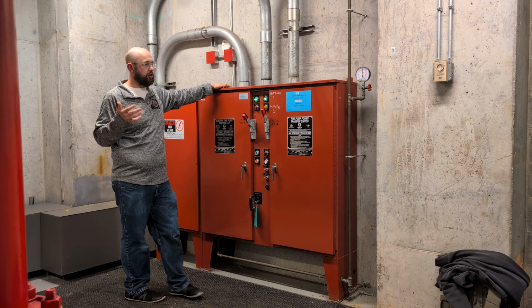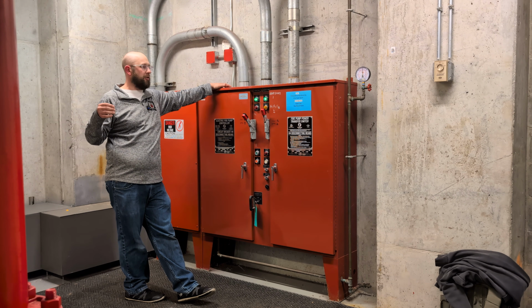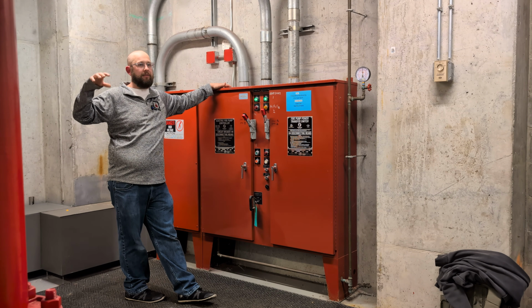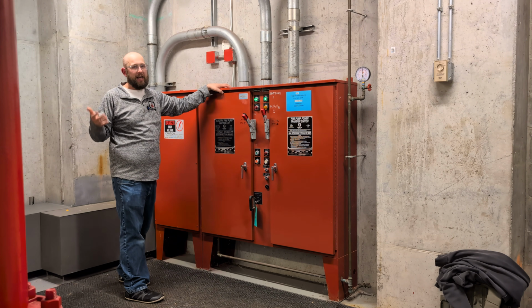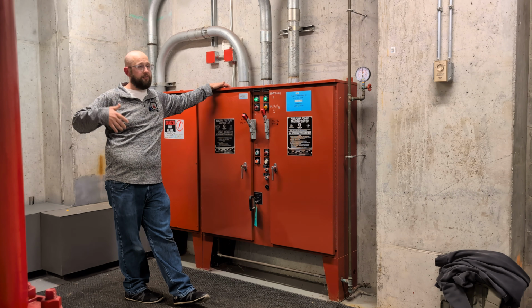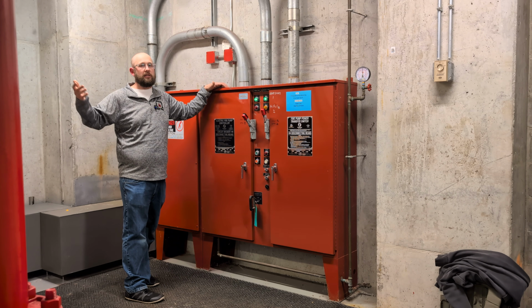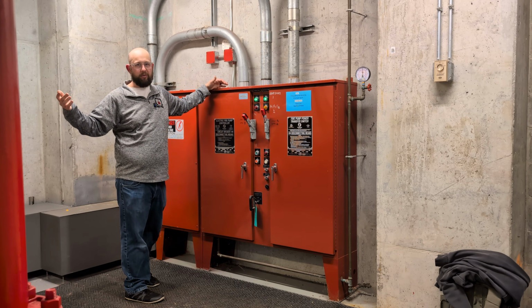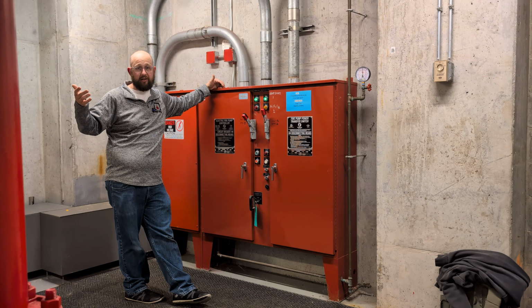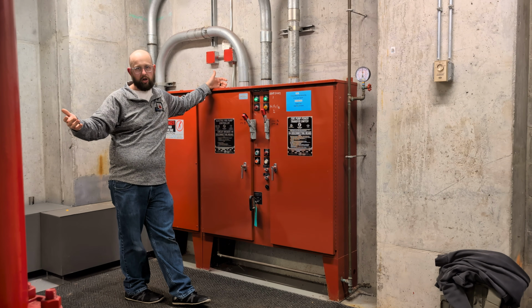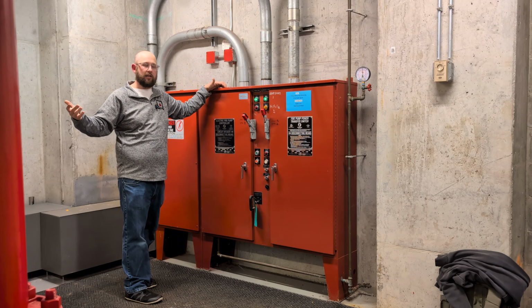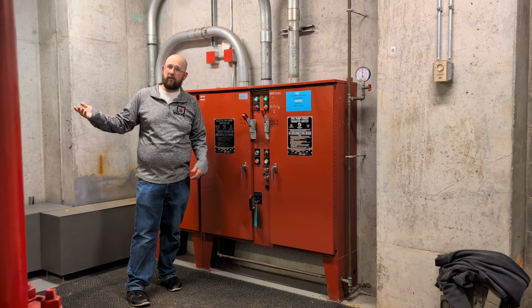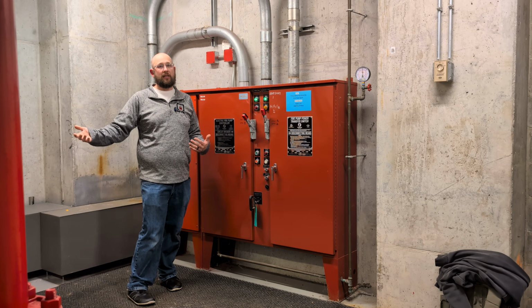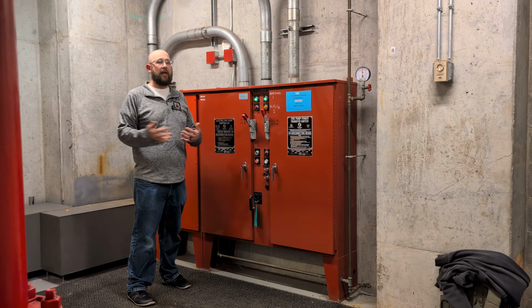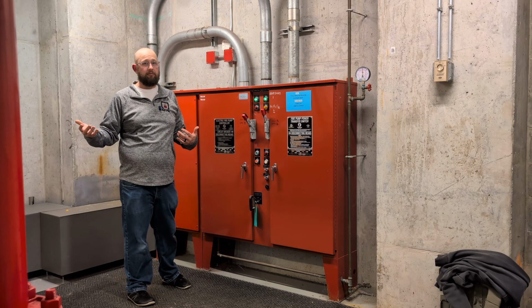And then one thing I just want to talk about as we're talking about monitoring alarms is many people think that a fire pump running is actually a fire alarm condition, when in this case it is actually just a supervisory condition. We're not going to set off our notification appliances and evacuate the building if the fire pump's running. Because we know in many cases, we're going to be running our fire pump to test it on a weekly or monthly basis. We don't want to have an alarm condition every time that happens, right? The real alarm condition in that case, if we had a sprinkler operate, would be our water flow switch on our sprinkler system, not the fire pump running itself. So just a little clarification, a lot of people ask, well, I should have my fire pump running be my alarm condition. And no, that's not the case. They're all supervisory signals that then are going to send somebody to come check out the condition and rectify it.